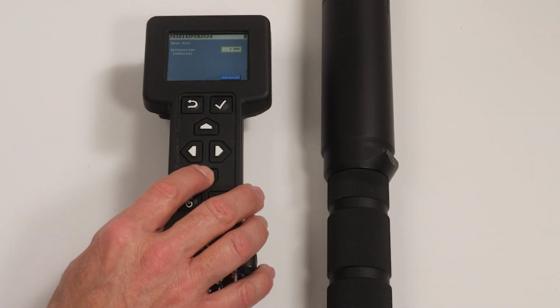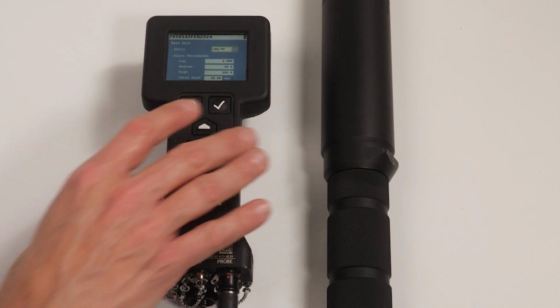A vehicle or shelter can attenuate or reduce the amount of radiation the base unit is detecting. The attenuation factor compensates for this reduced amount of detected radiation and allows the base unit to report the radiation reading as if outside the vehicle or shelter. Valid range for an attenuation factor is 1 to 1,000. This setting is generally calculated by an experienced nuclear physicist, so we recommend not changing this value unless you've been given guidance on what factors to use. Highlight the Advanced button and press Enter to change base unit specific settings.